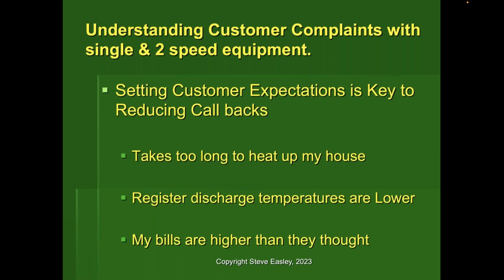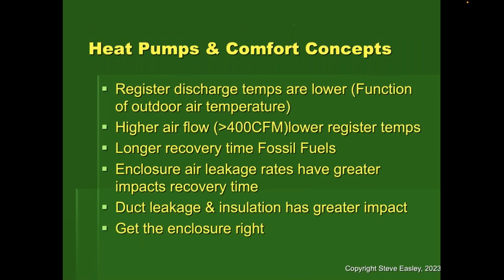So it's really important, number one, wherever possible, to utilize inverter-driven equipment, because you can better match the loads of the home to the equipment. But also make sure you explain to customers that you just can't turn your thermostat up and expect your home to get heated in 15 minutes. Also recognize that the discharge temperatures coming out of the registers might be a little lower, particularly if the HVAC contractor didn't take the time to seal the ductwork, or maybe didn't take the time to insulate the ductwork. So let's just say, and I'll explain this in a little more detail, show some real world examples. So, Mike, do we have any big questions?